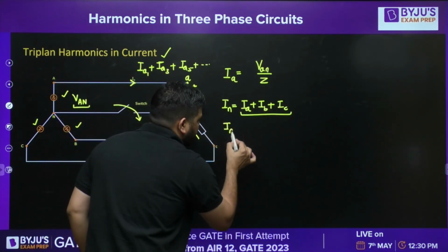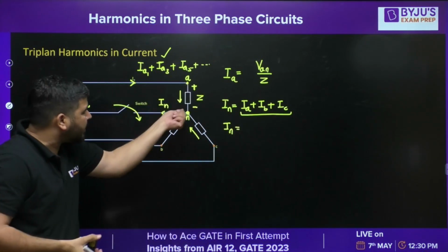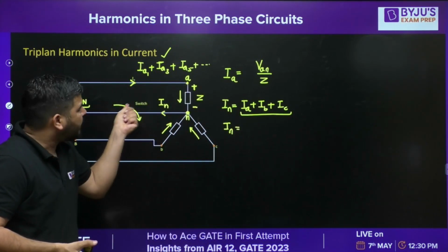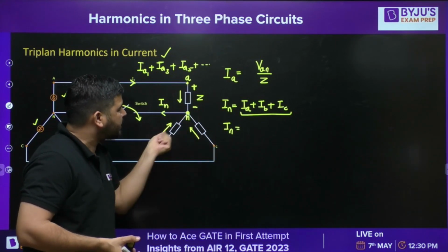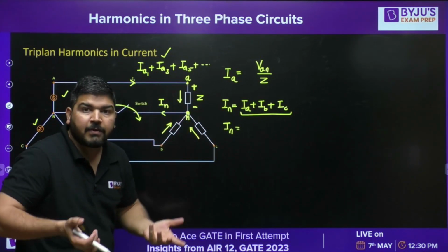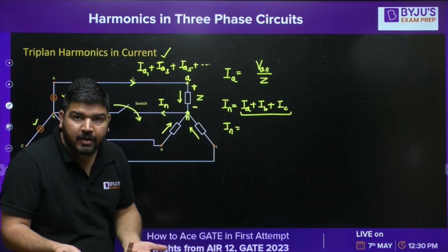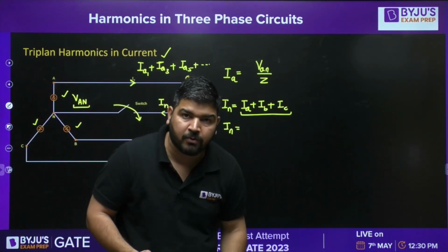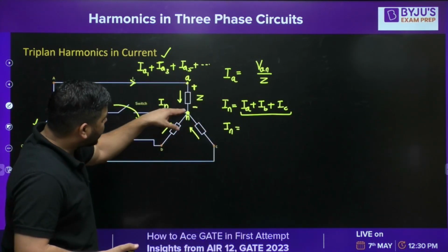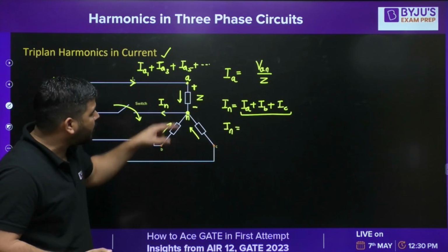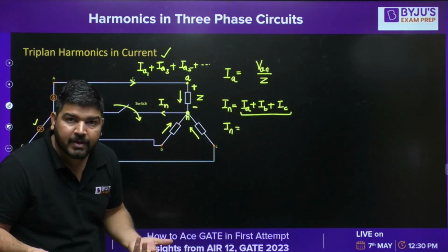So it will add up, it will not be zero - IN will contain only triplet harmonic. The fundamental component of each phase will cancel, the fifth harmonic will cancel, the seventh harmonic will cancel, because they are 120 degrees apart. But the triplet harmonic will not cancel - they add up because they are in the same phase.